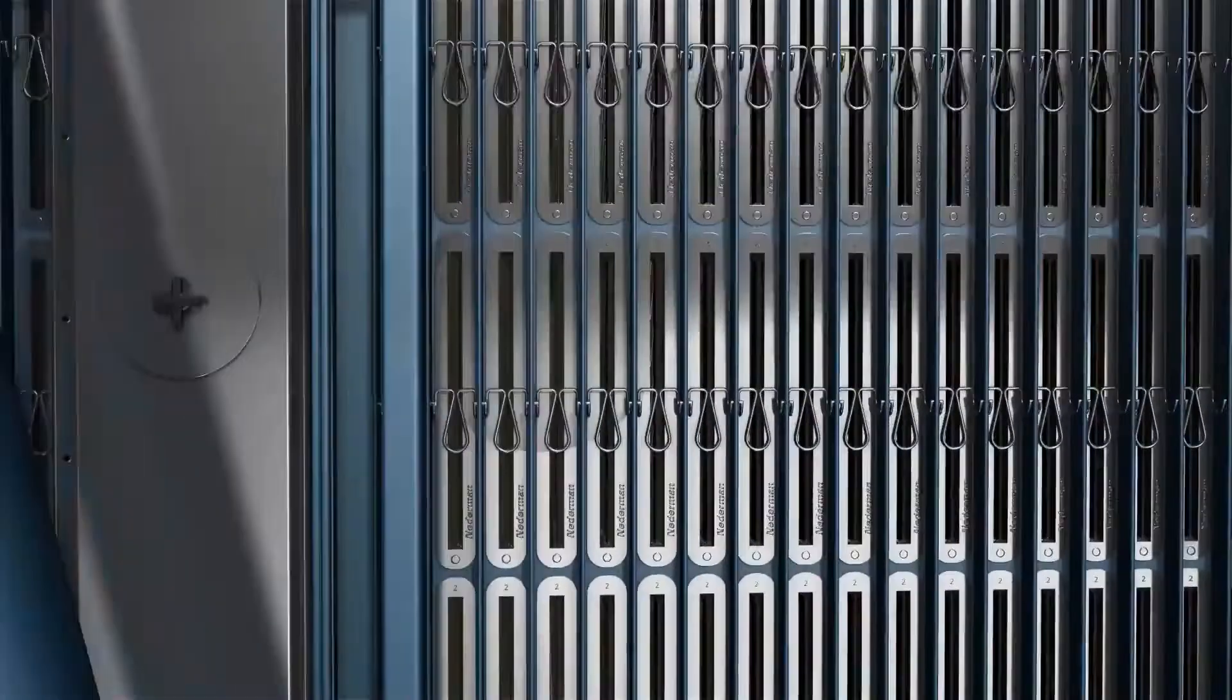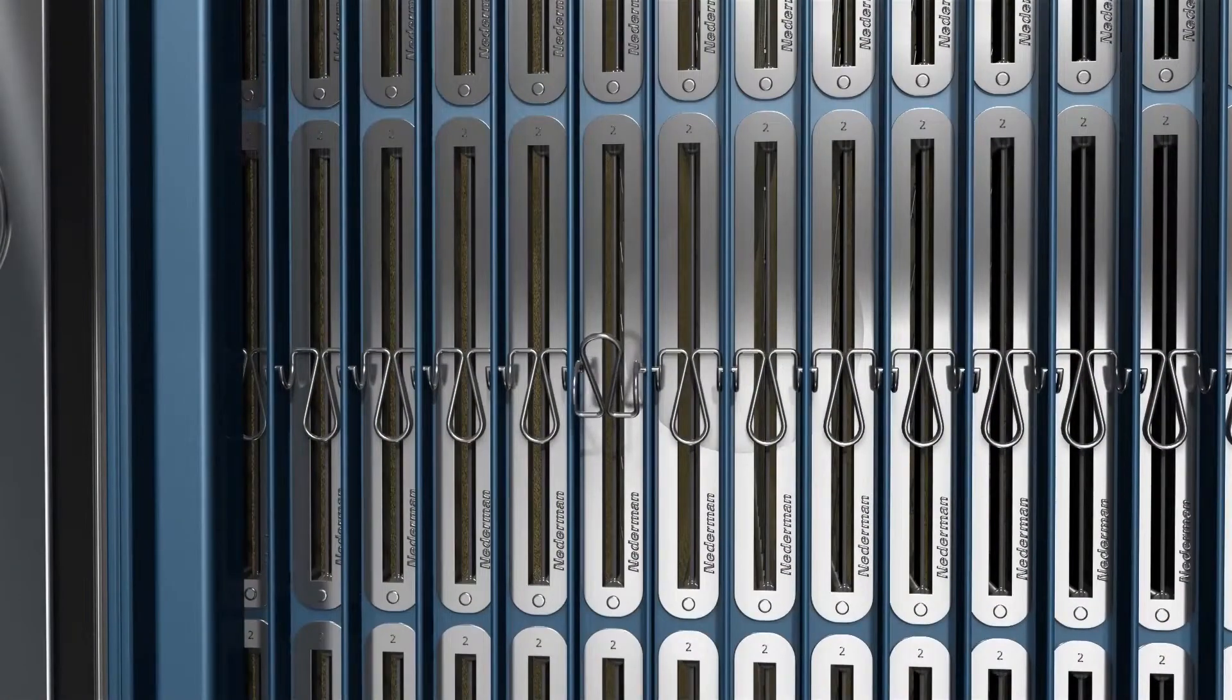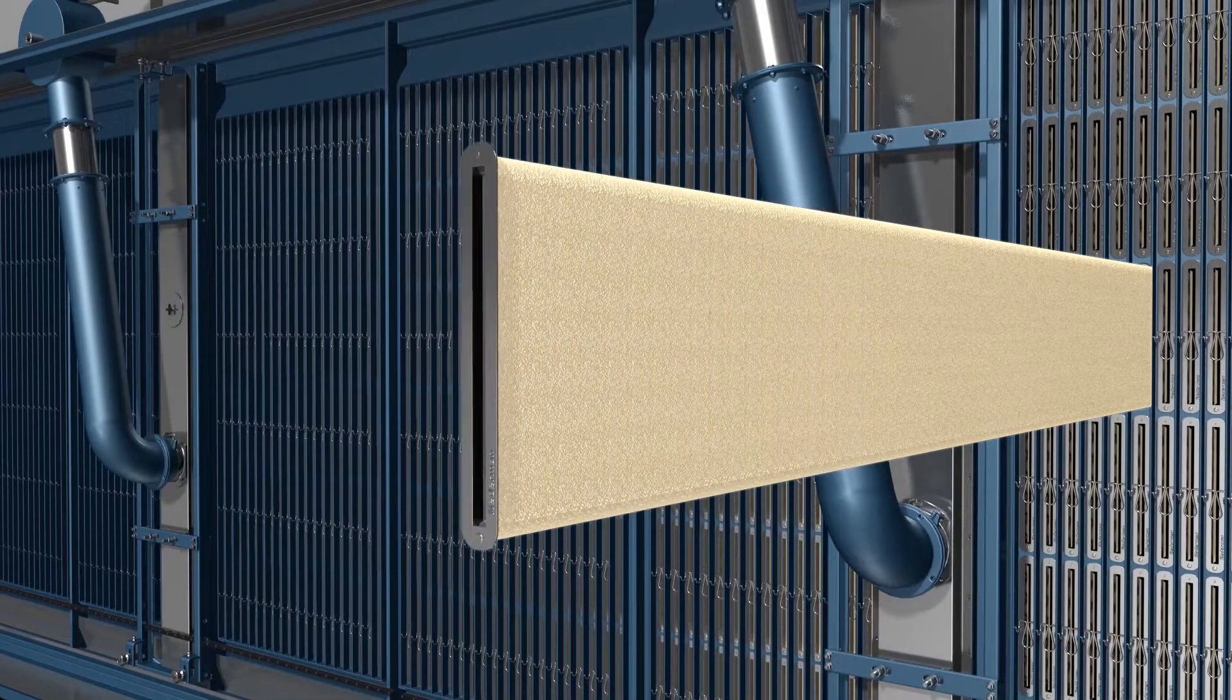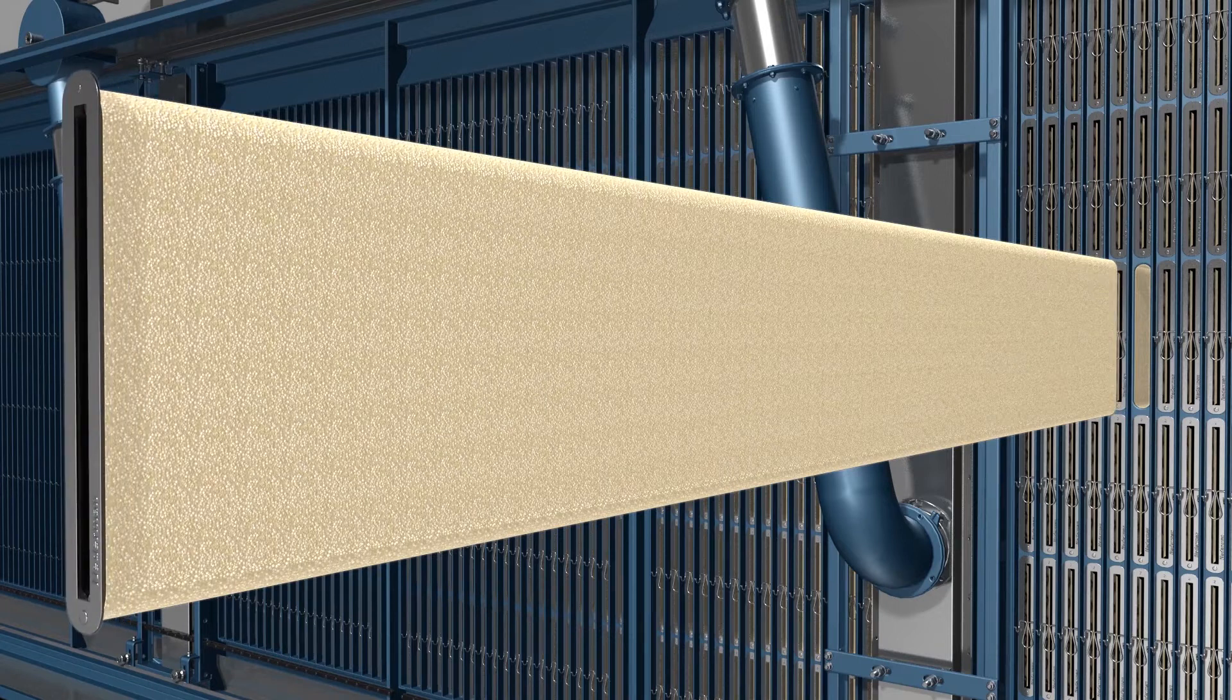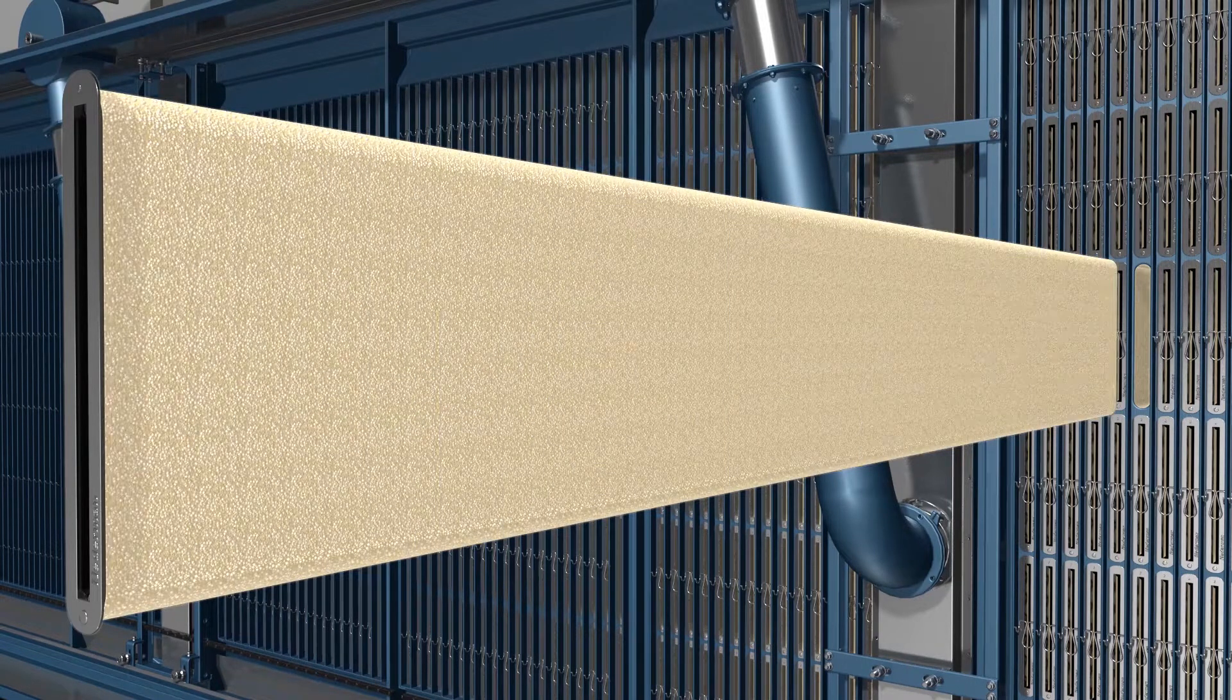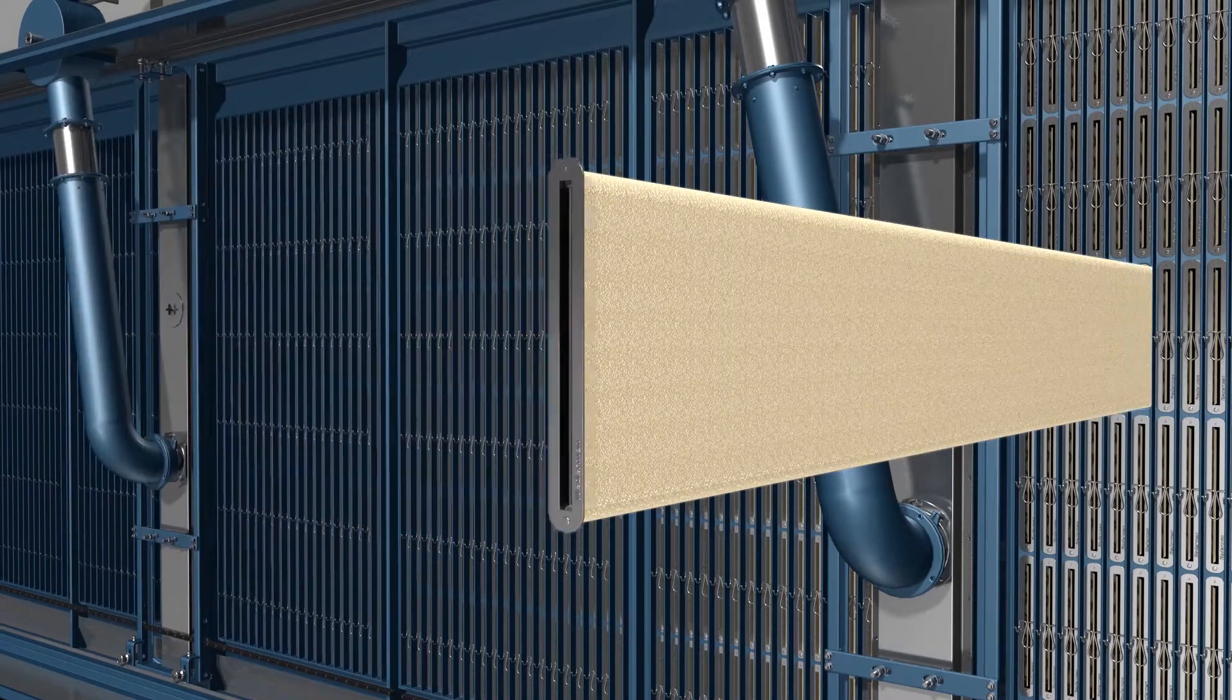Maintenance staff can access the filter bags on the clean air side of the filter. The leg spring is loosened and the filter bag along with the spacer mat can be removed. This makes the maintenance of the filter bag safer and easier compared to a top removal of filter bags in typical PulseJet filters.